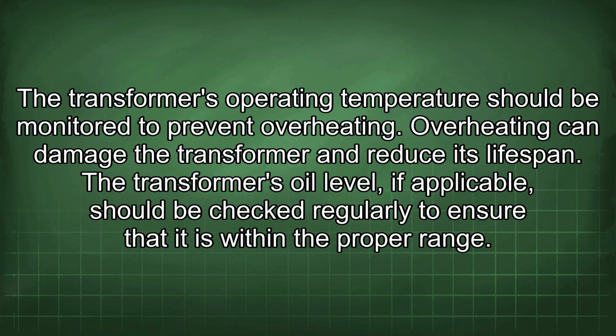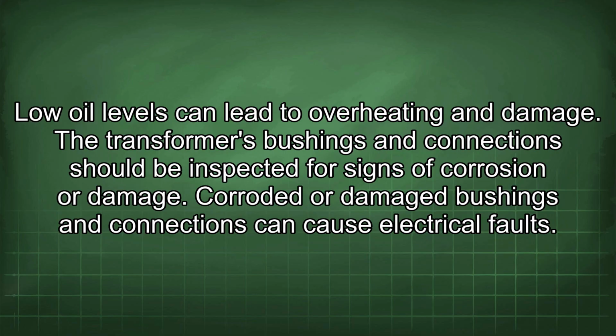The transformer's operating temperature should be monitored to prevent overheating. Overheating can damage the transformer and reduce its lifespan. The transformer's oil level, if applicable, should be checked regularly to ensure that it is within the proper range. Low oil levels can lead to overheating and damage. The transformer's bushings and connections should be inspected for signs of corrosion or damage. Corroded or damaged bushings and connections can cause electrical faults.